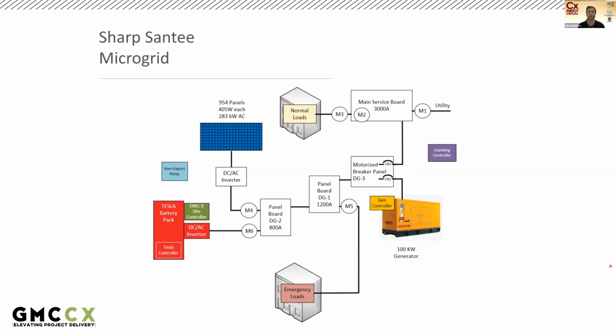Another note is that there's no true ATS. The motorized breaker panel DG3 has these 2 breakers, CB1 and CB2, interlocked. So there's no ATS because both of these breakers have to be able to be open at the same time. However, they can't obviously be closed at the same time because we can't export generator power to the grid. So similar to the battery, we can't export battery to the grid, we can't export generator power to the grid, we can only export solar power to the grid.